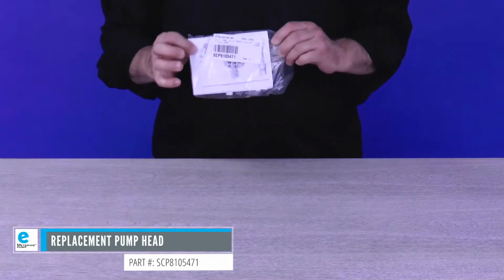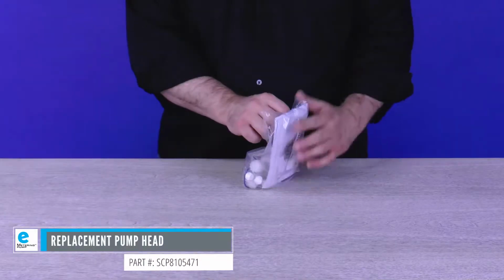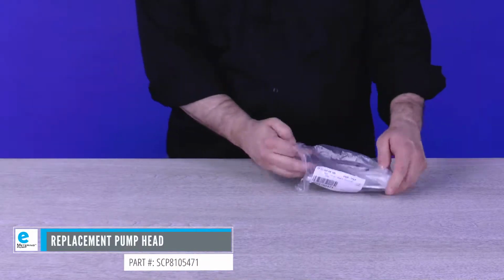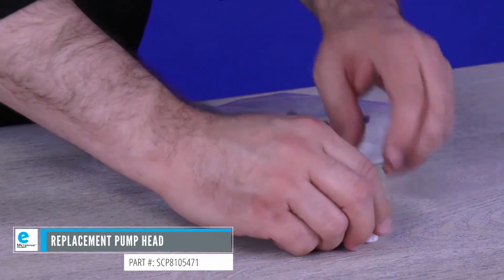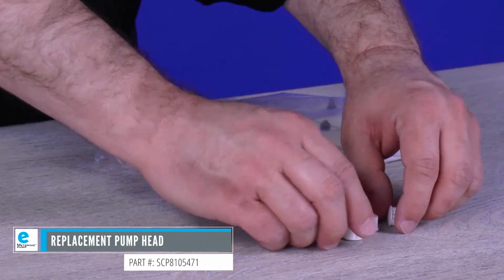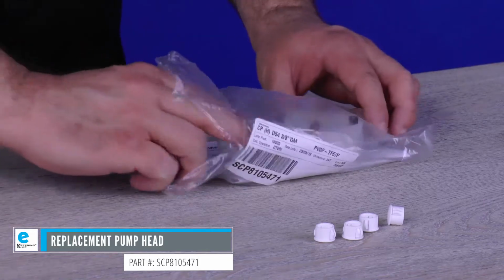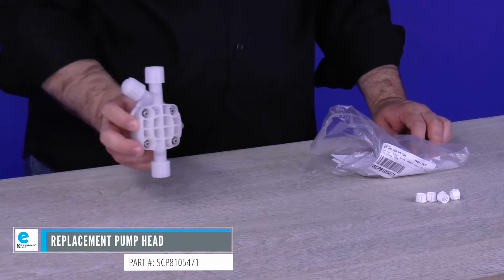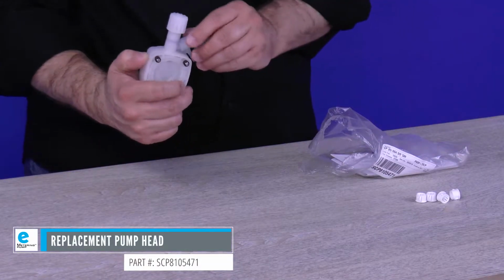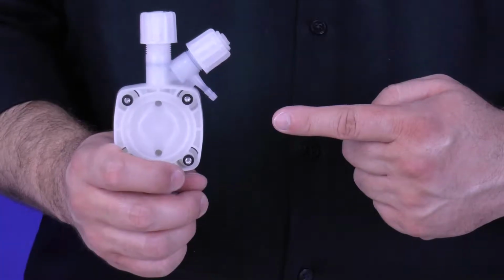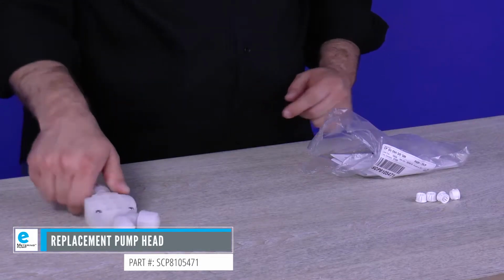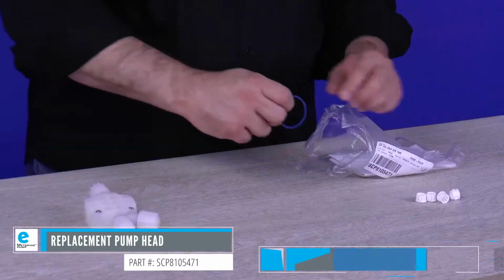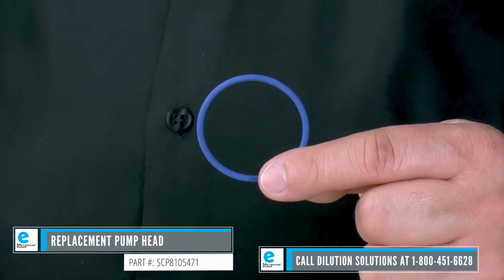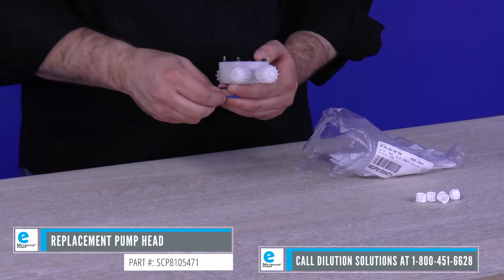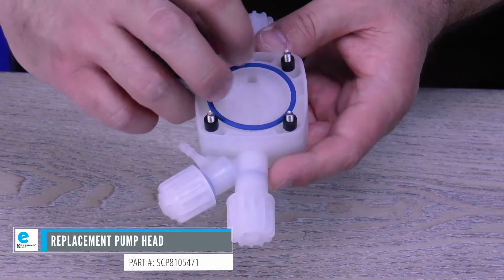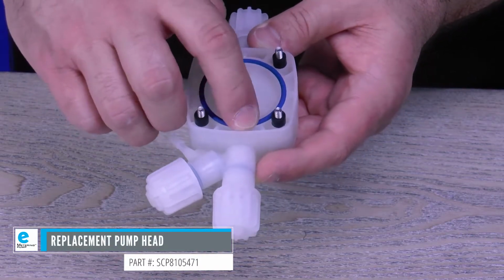Locate the pump head bag along with the 4 new small white caps. Take the 4 new small white caps out of its bag and set the white caps aside. Take the new pump head out of its bag and turn the pump head over so you are looking at the back side of the pump head. Check to see if the large blue O-ring sits in the groove. If not, look to see if it fell out in the pump head bag or call Dilution Solutions for assistance at 1-800-451-6628. Insert the large blue O-ring into the groove on the back side of the pump head.